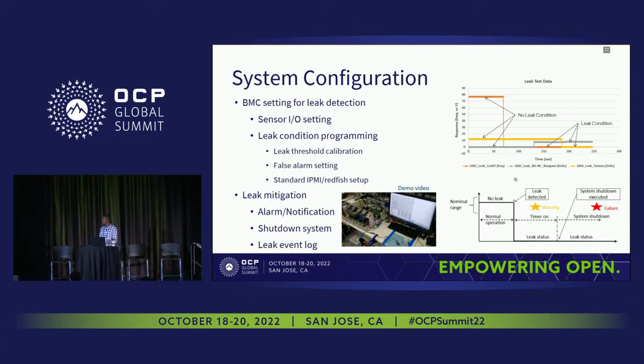For the BMC configuration, this is some of the testing we did. As you can see, these sensors, the signal is kind of a discrete signal. For leak condition, it shows a straight line, and then the same for no leak condition. And when a leak is detected, the state changes immediately. So this is kind of straightforward for the BMC folks to do the integration. All they have to do is map each of those pins to the right wiring, and then program it based on the appropriate threshold setting. And you need to do the threshold setting, that way any kind of false alarm from the sensor we can prevent.